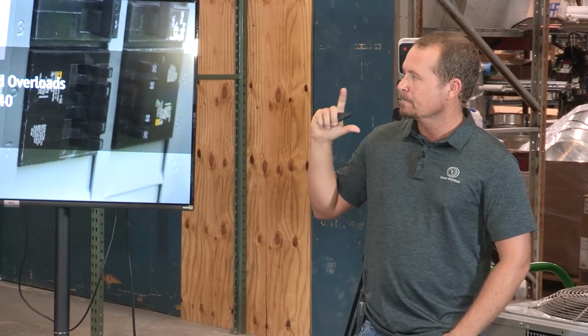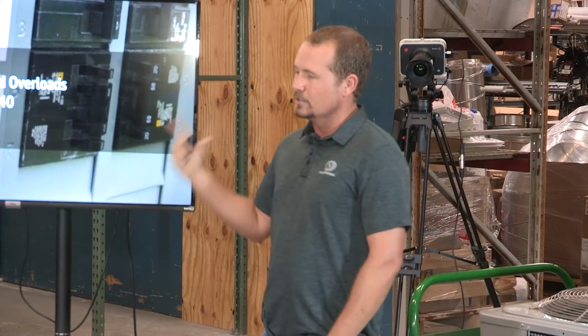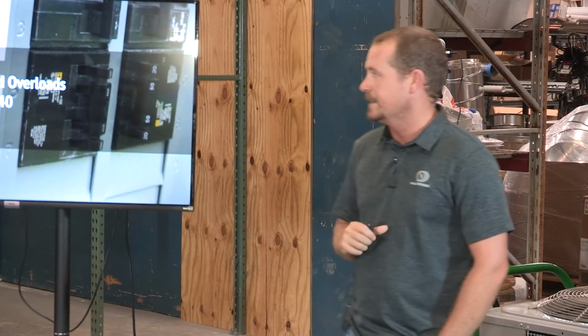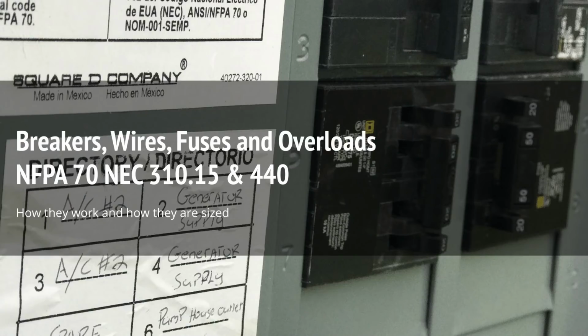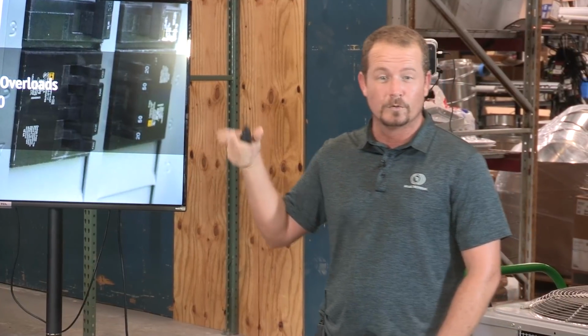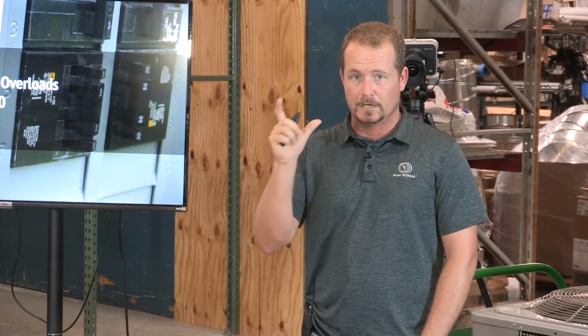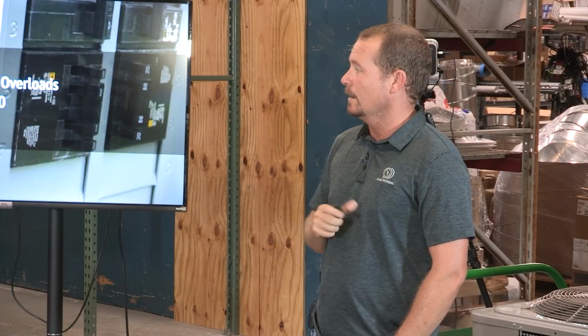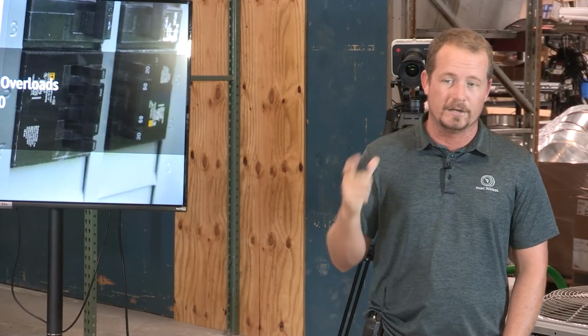But ultimately, you can go and check for yourself by going to 310.15, specifically table B16. So brackets B, brackets 16. If you Google that, you'll pull up like 1,000 of them. That is the wire sizing, the conductor sizing segment of NFPA 70. And then section 440 is specifically for air conditioning.